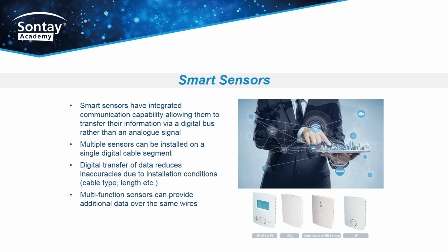Advances in technology have given rise to increased functionality from smaller devices. Sensors with built-in microprocessors now provide multiple functions in a single unit, complete with communication capabilities. Digital technology allows all values to be passed down a single bus cable, making it possible to daisy-chain sensors, reducing installation time and cost. Values are digital and are therefore not subject to issues such as voltage drop along the connecting cable length.